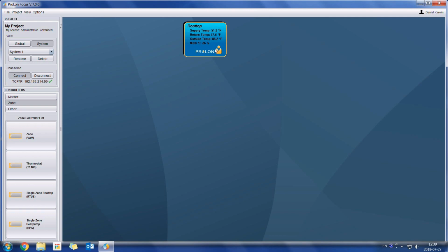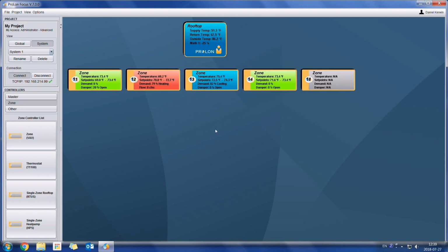If I simply right click on the rooftop controller, we go to Get List. If I click on this, it's going to put a call out to the network, and all the zones who hear the call will answer back. And there we go. So here I have 5 zones which just popped up. Each zone, we can see the information. So we can see what the space temperature is, what the set points are, what is the demand of that zone, and what is the damper position or the actual flow.